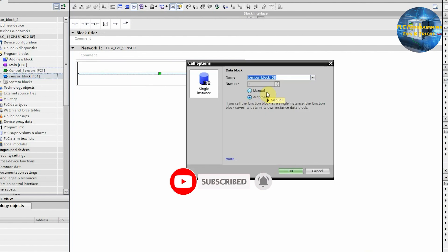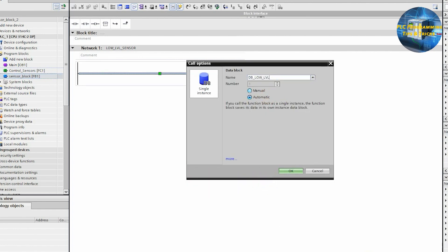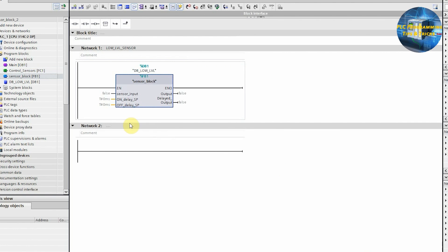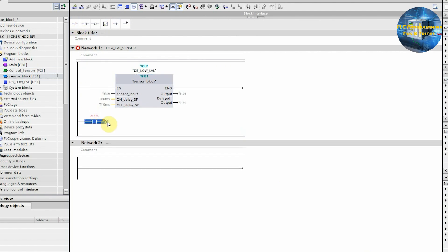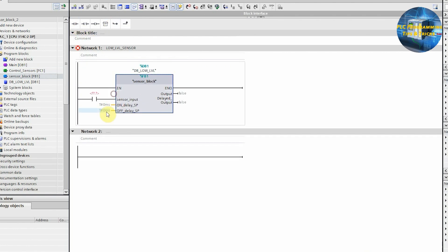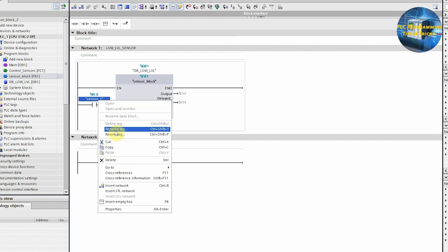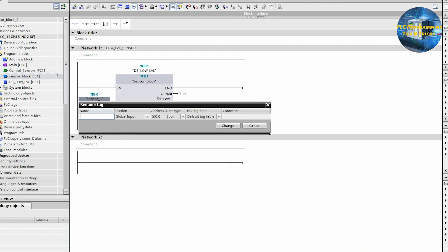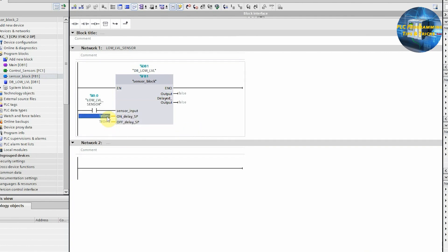We will drag and drop the sensor block onto the ladder. This will create an instance for this function block, which we can name as DB Low Level. Next, we will insert a normally open contact at the sensor input of this block and assign it I0.0 input of the PLC, as we have connected the low level sensor at I0.0. Next, we will set the on delay and off delay time as 500 milliseconds.